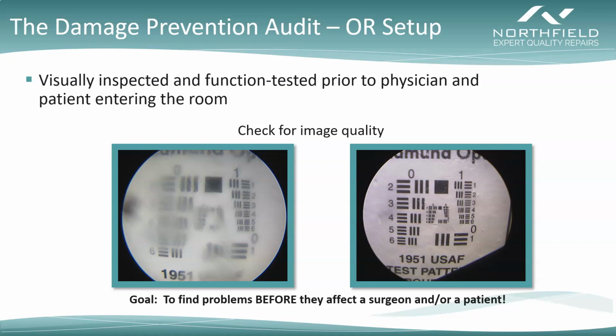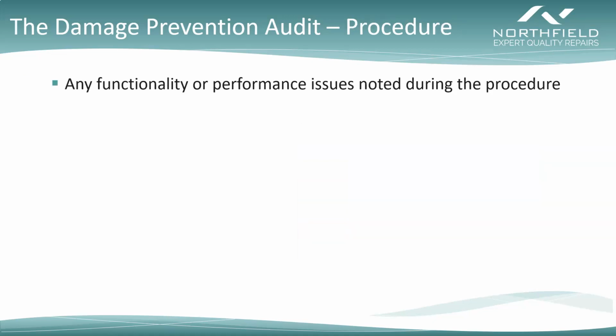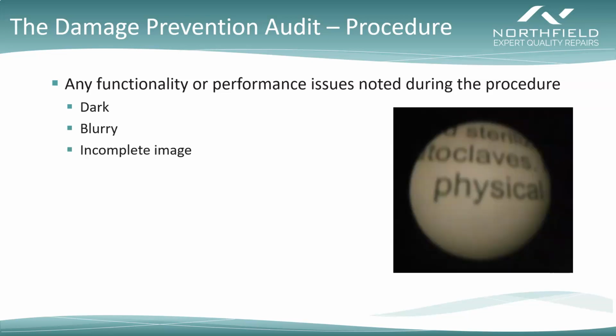So any time that we can catch a problem with the device before the physician and the patient get into the room, that is our goal. Now, during the procedure, we always want to make note of any functionality or performance issues that are noted during the procedure, and usually it's the surgeon that's going to catch these. They might complain about it being dark, blurry, or maybe even an incomplete image. So in this particular instance, we would consider this a failure to catch the issue earlier, but sometimes the surgeons do notice things that only could be noticed during the procedure. So keep that in mind and make note of that anytime something like that comes up.